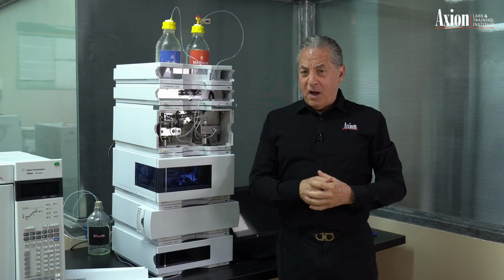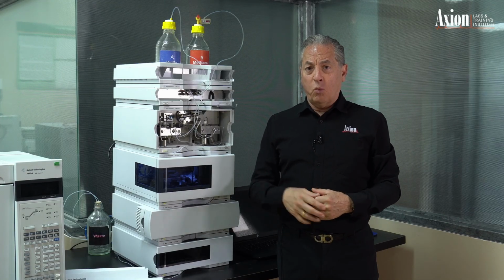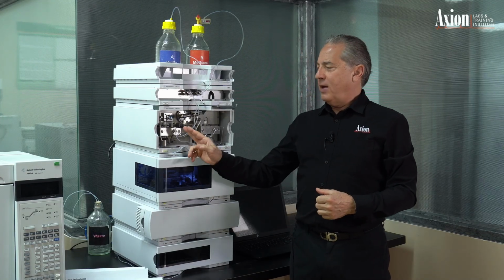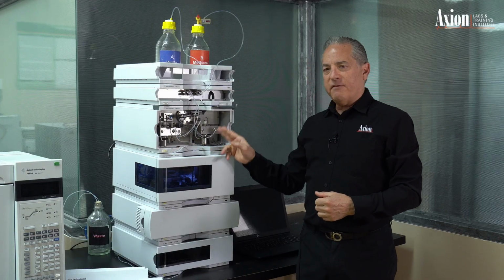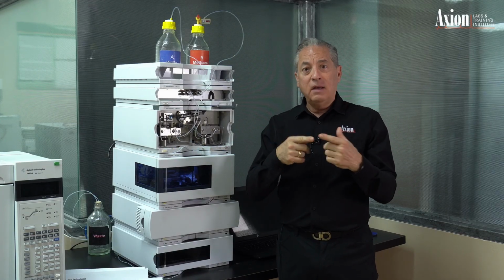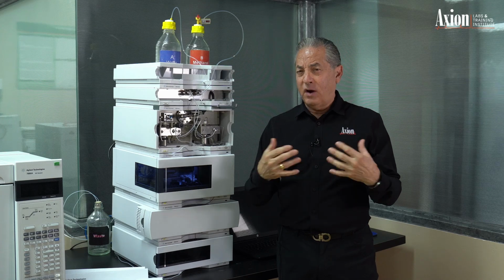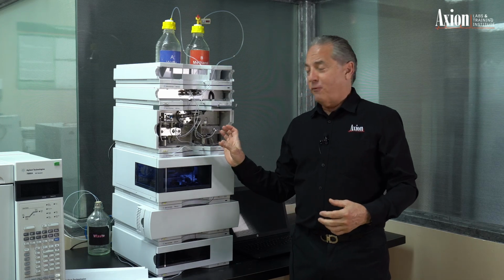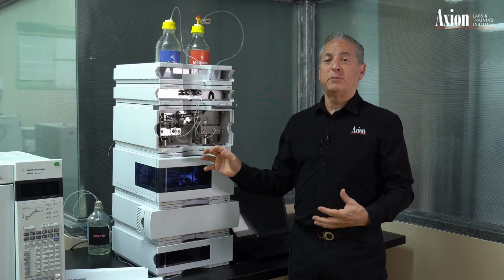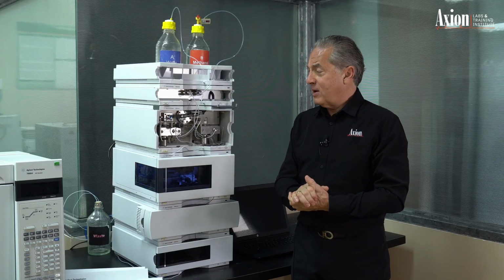So if I want to run 50-50 methanol water at 1 ml a minute, I would set pump A to half a ml a minute, pump B to half a ml a minute, and then the output is combined to give 50-50 methanol water at 1 ml a minute. So you get the idea. Fortunately, the pump does the math for us. We just tell it the percentage, and it figures out how to make that happen.